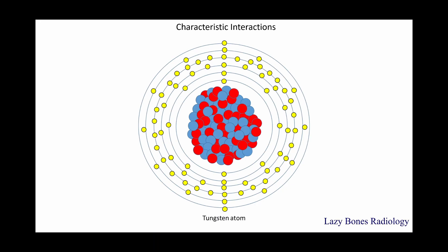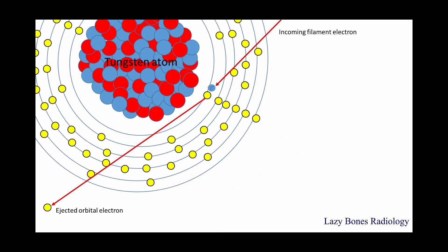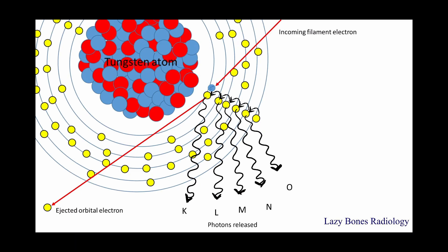Now let's look at how characteristic interactions work. The incoming filament electron strikes an inner shell electron of the tungsten atom, causing the electron to be ejected — known as an ejected orbital electron — and the filament electron continues on its path. This collision causes a vacant spot inside the inner shell of the tungsten atom, which causes a change in charge. In order to maintain balance, neighboring electrons shift towards the center, releasing energy known as a photon. As one electron travels towards the center, the vacant spot moves from the center to the outer shell because the electrons keep shifting inward. Every time there's a shift, a photon is released. This is known as a characteristic cascade.